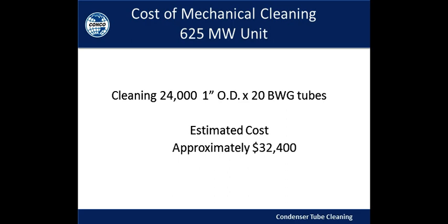Let's take a typical 625 megawatt unit, right? From the curves and the surface area and the heat transfer calculations, I can determine that approximately 24,000 1-inch 20 tubes would be required to meet that demand. Estimated cost to mechanically clean that would be $32,400.